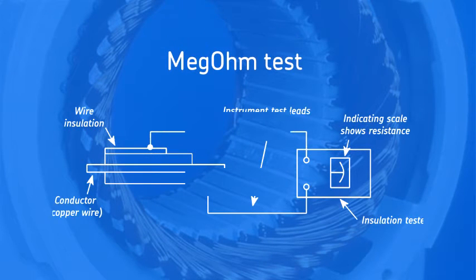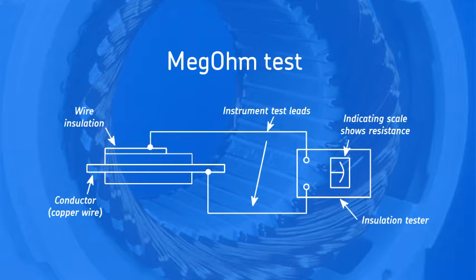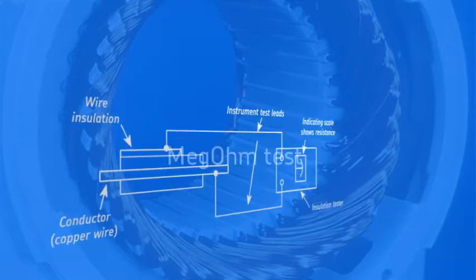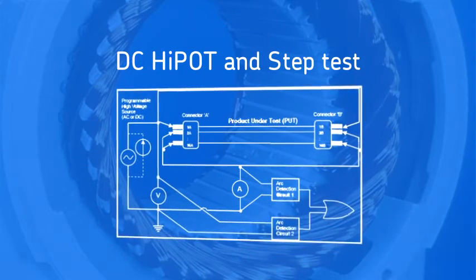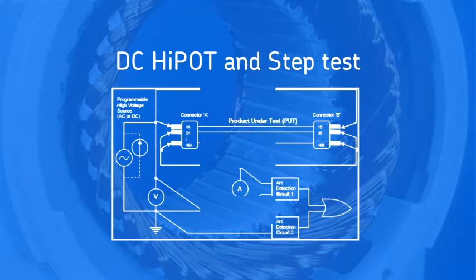Ground wall insulation strength is measured with the meg-ohm test at low voltage, but this test misses many ground wall insulation failures. A better test is the DC high-pot and step tests, which measure insulation strength at higher voltages.